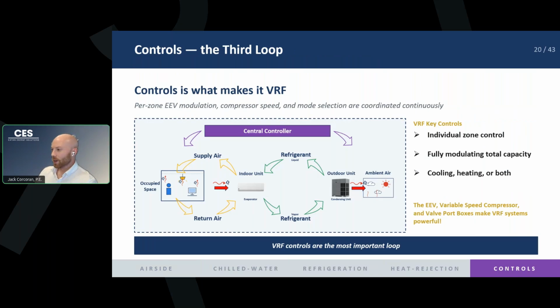So the 3rd loop, right? Our controls loop, we haven't really talked about it yet, but that is actually what makes VRF so powerful, right? If we can modulate our EEVs and we can modulate the compressor speeds, dial it in exactly to what the demand is, we're going to have a really smart system that is very energy efficient, right? And so every single zone is going to have its own temperature control with the EEVs, and those EEVs are going to talk to our compressor to basically have more efficiency, right? We're not running all out unless we need to run all out. We're running at part loads, we're running at part speeds, and we're not using as much electricity in this situation.